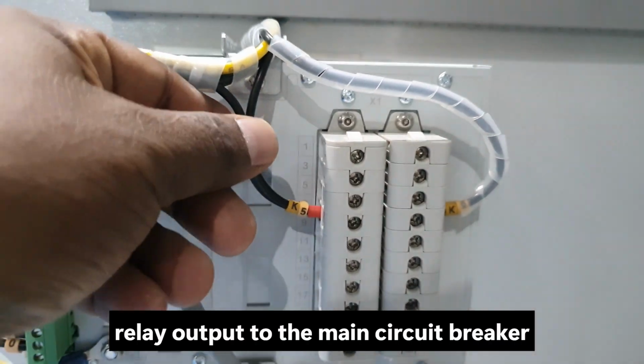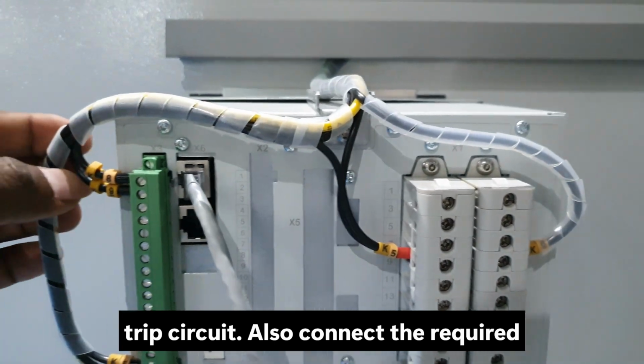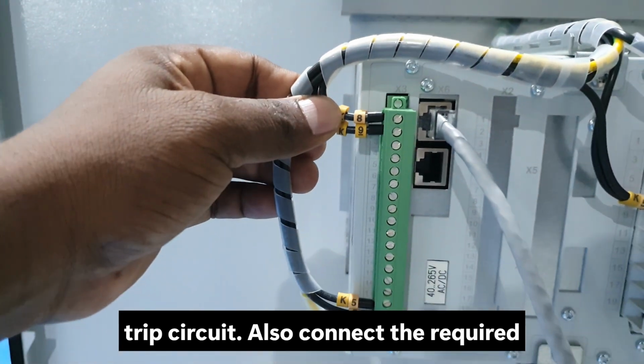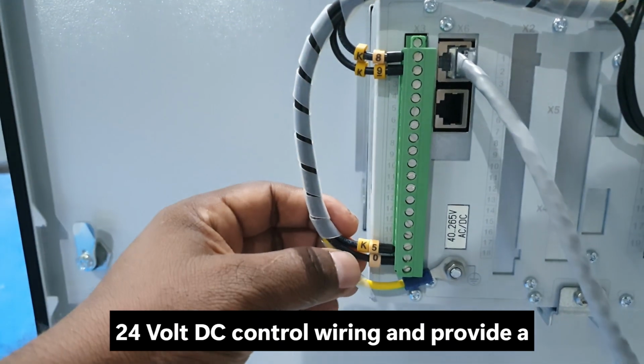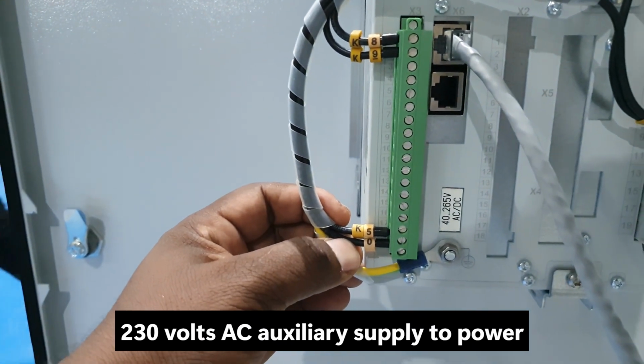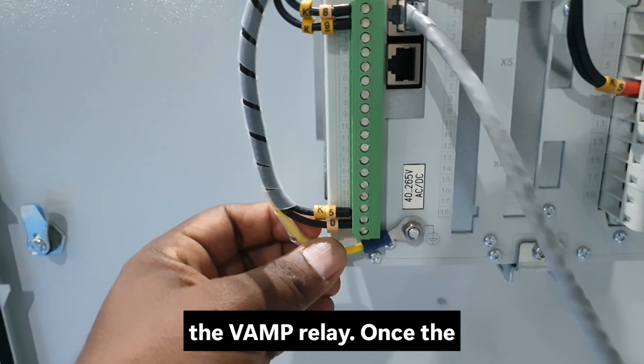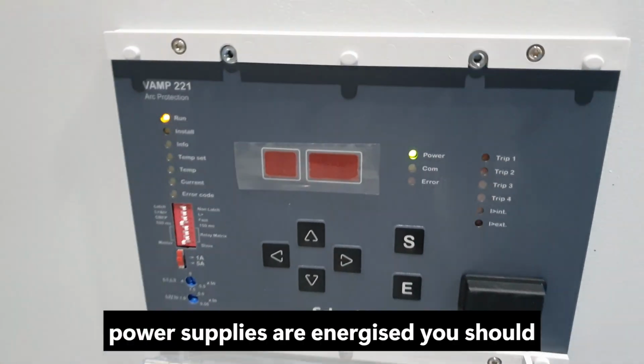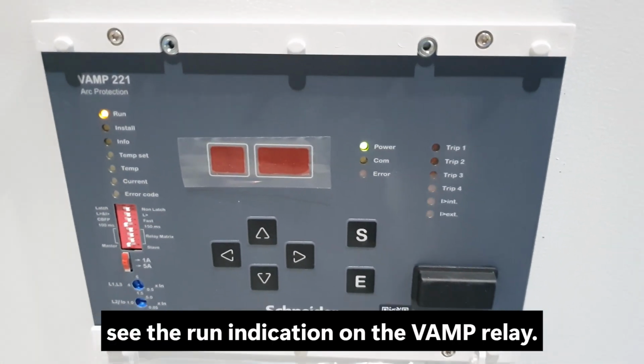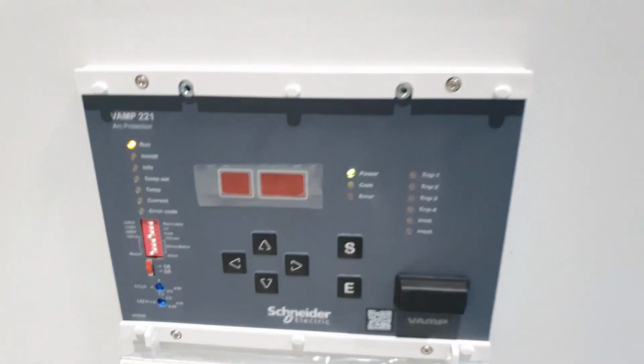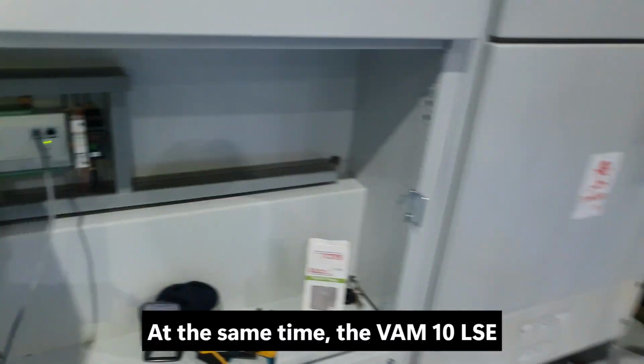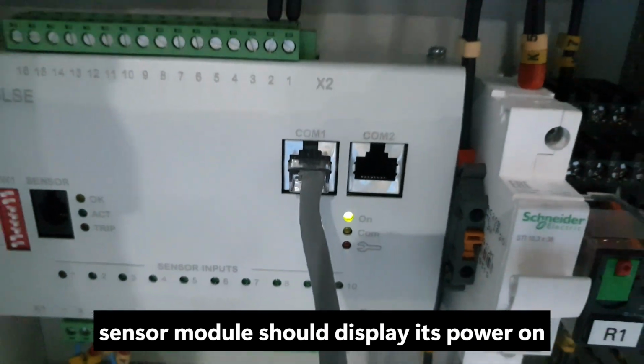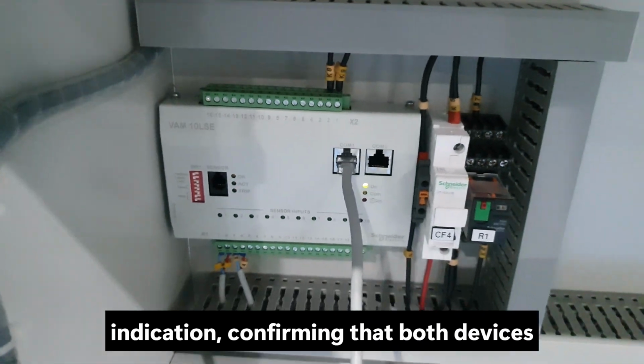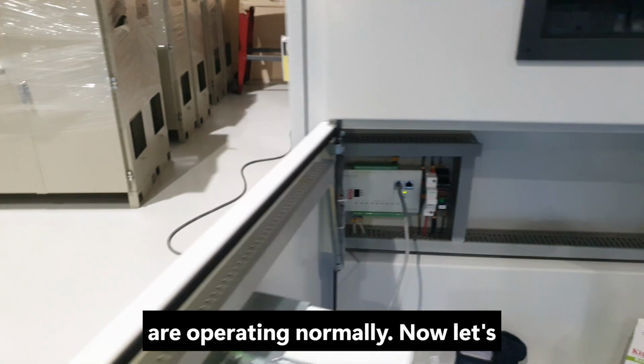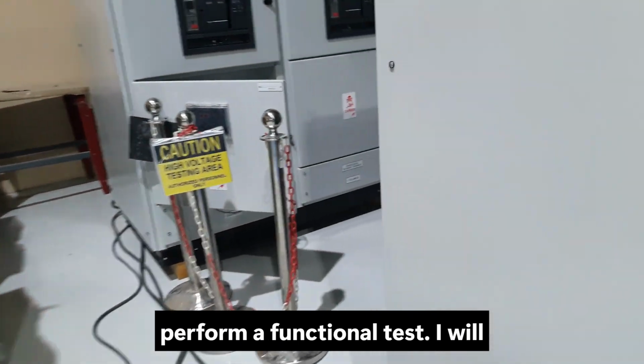On the VAMP 221 relay, connect the trip relay output to the main circuit breaker trip circuit. Also connect the required 24-volt DC control wiring and provide a 230 volts AC auxiliary supply to power the VAMP relay. Once the power supplies are energized, you should see the run indication on the VAMP relay. At the same time, the VM10 LSE sensor module should display its power on indication, confirming that both devices are operating normally. Now let's perform a functional test.